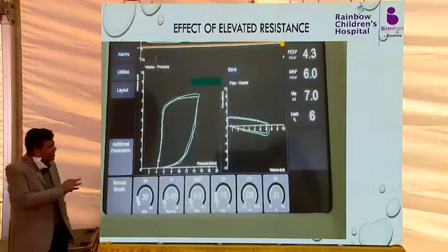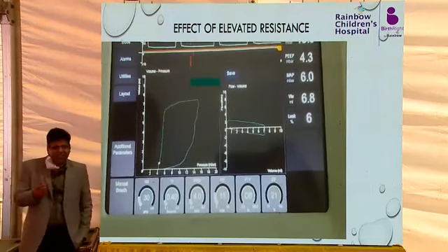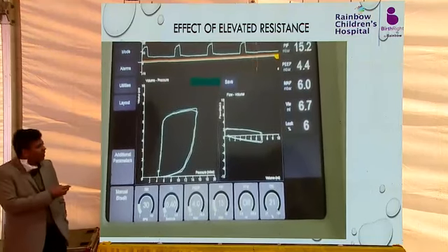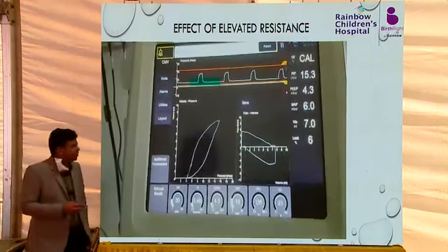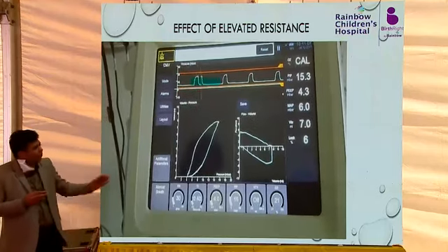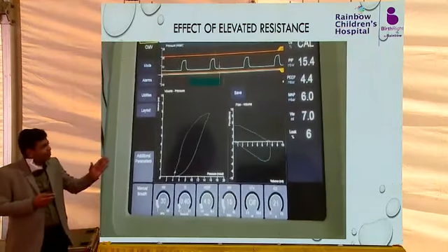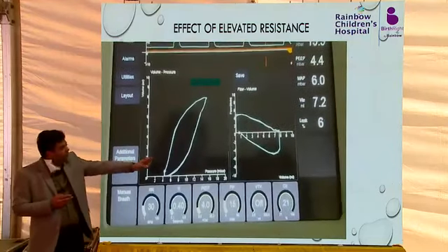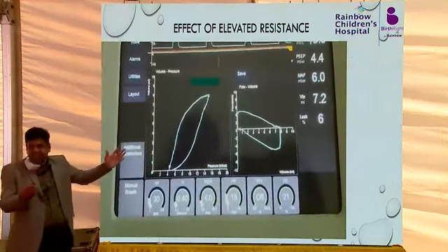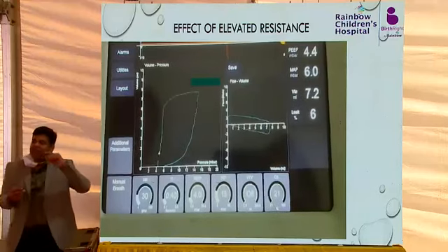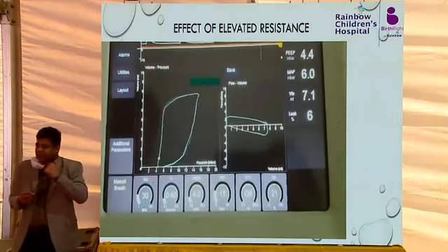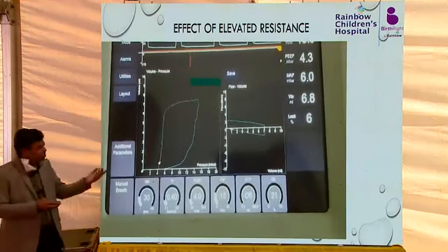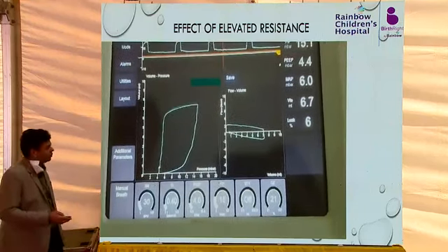So this is on a test lung. When we try to increase the resistance, we will do all this exercise in the workstation. By doing that, it happens like this. Sometimes if you find that the waveform was previously normal and now the flow volume loop is abnormal and the pressure volume loop hysteresis is widened, you can think that there may be kinking in the endotracheal tube. Sometimes the endotracheal tube is too small in size, so you can think about that.